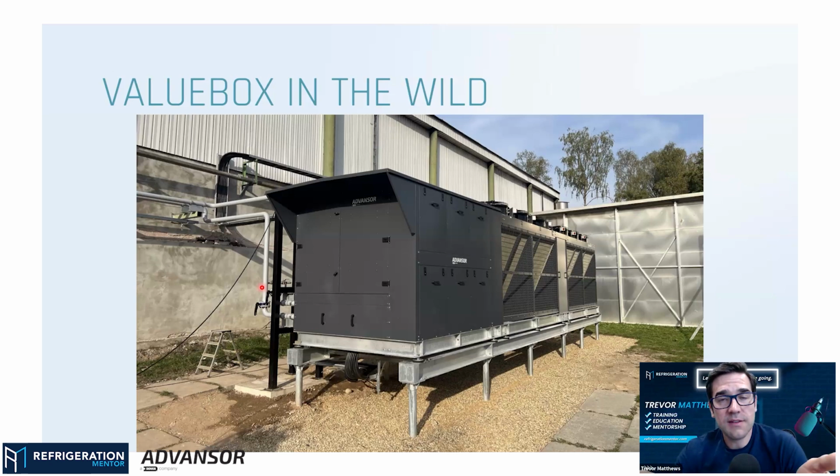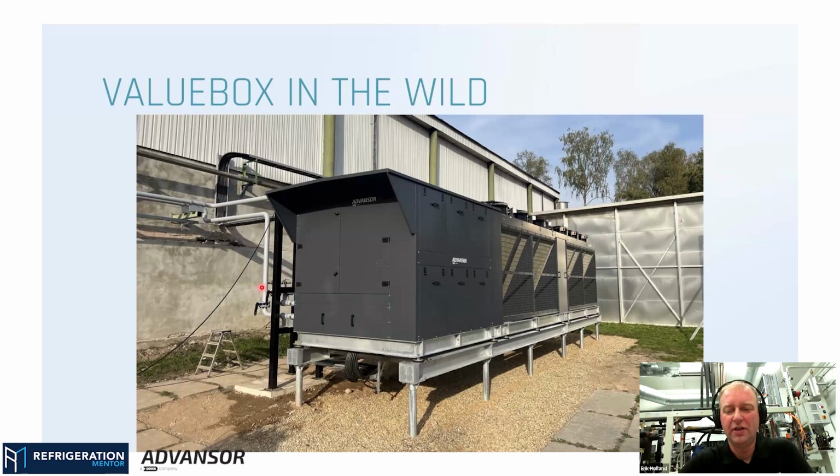But yeah, it does. And I know, because even 2 years ago when I was at Chillventa talking with you guys, and even all the other manufacturers in Europe that are using ejectors, a lot of people think it's difficult to use in North America, but it all depends on the application. Here in Canada, in a supermarket transcritical booster system, you don't need ejectors, if you're just doing refrigeration. But when you're using a heat pump now here in Canada and district heat, ejectors might be the thing that you need in this cold climate. It's a definite tool in the toolbox.